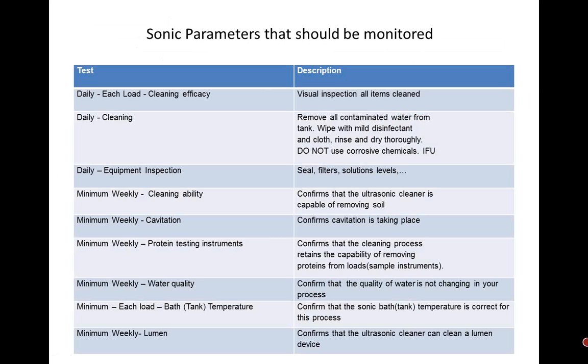Weekly cleaning ability confirms that ultrasonic cleaning is capable of removing soil. Again, that's independent from the cavitation. Make sure the cavitation is taking place.